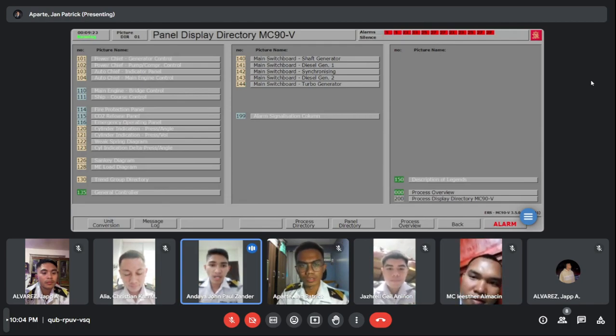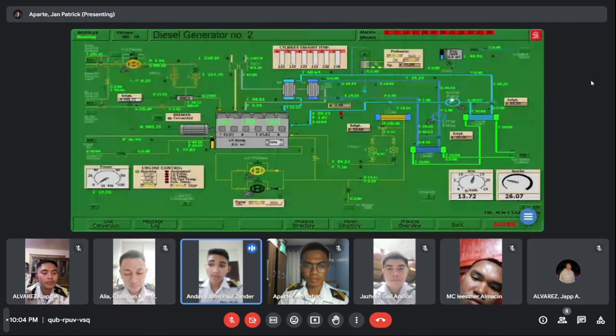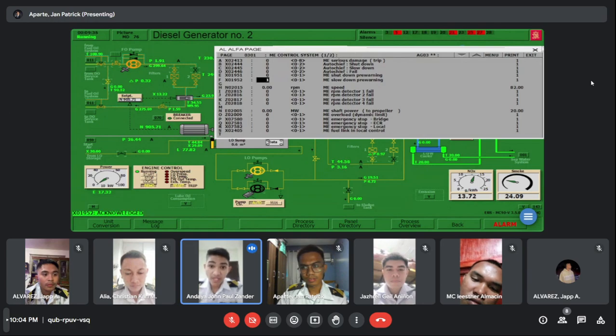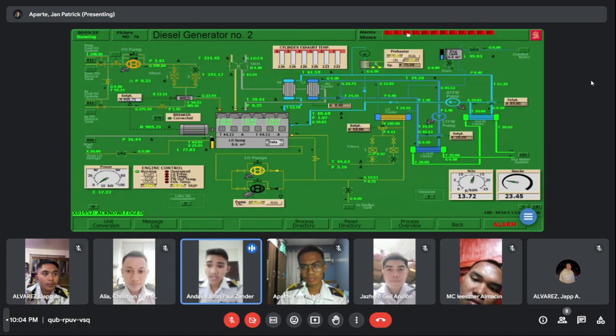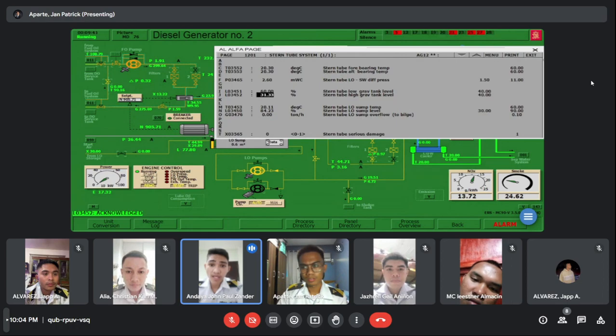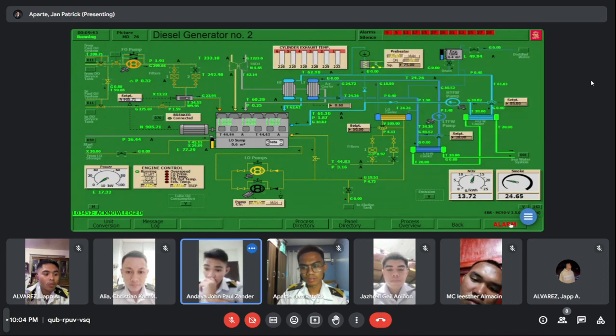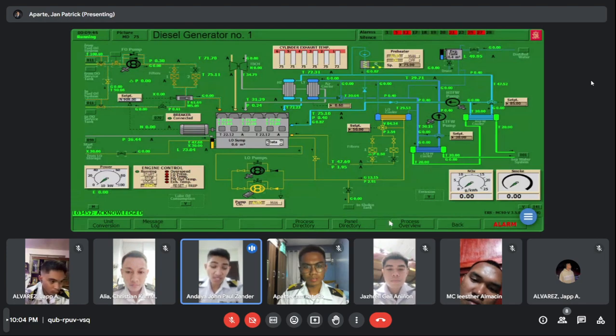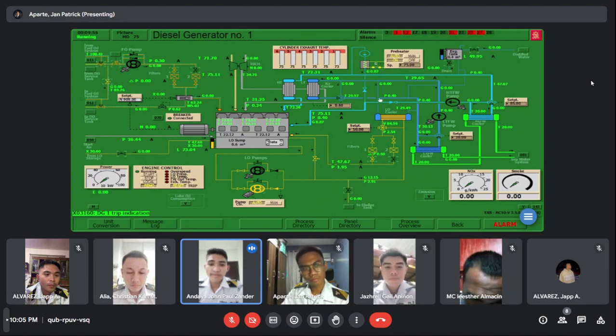And then we just wait for 10 minutes. After 10 minutes, that's the end of the assessment. Just to make sure that you all rectify the filters, everything must be reset. Then no high temperature on the bearings, and also no trips and alarms on DG1 and DG2 after 10 minutes. So that's the end of the assessment. Thank you and God bless.